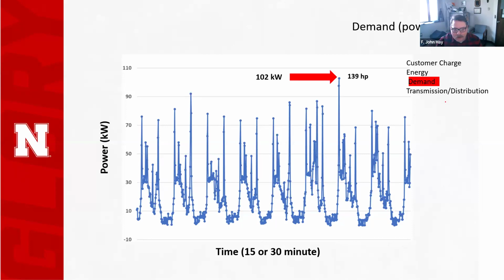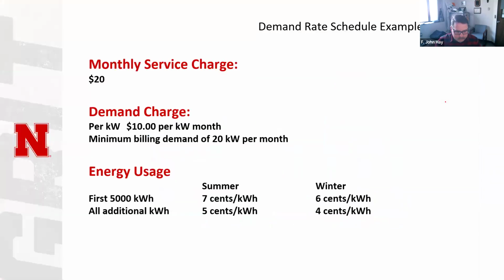You turn them on and they draw a whole bunch of power for a very short amount of time, maybe a couple of milliseconds. But this 15-minute rolling average is what they're usually measuring that on, so that kind of gets rid of that. But the challenge with demand is that it's harder to find out exactly when that demand was set and what was running when that demand was set, because I'm usually not monitoring my systems in that level of detail.